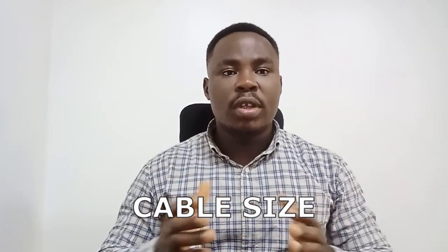Number three is cable size. For low voltage battery system, since the current is high, you will need thicker cables for your installation to be able to handle the large current. But for high voltage battery system, since the current is lower, you need thinner cables for your installation.